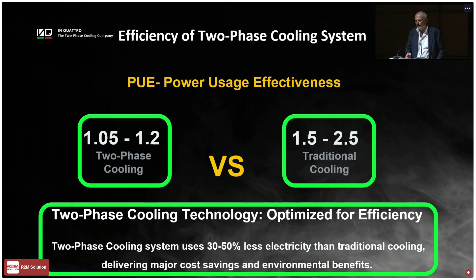Just to give you an idea, for example, if you put the external heat exchanger, called a dry cooler, which is a system that is not a chiller and doesn't use water, so you release the heat generated in the processor outside with this system. Then if you put this at 30 meters of distance from the data center, the PUE is about 1.07. So this is just to give you an idea of how important the design and the configuration of the data center is on this particular KPI. So with two-phase cooling system, it's possible to reduce the electricity consumption compared to the standard cooling technologies by between 30 and 50%.